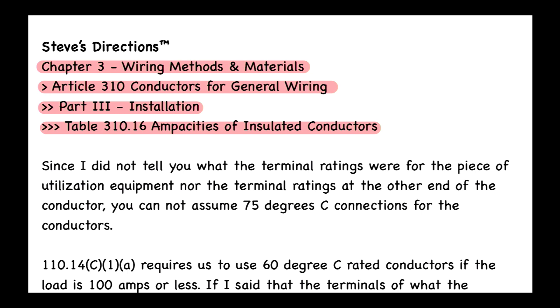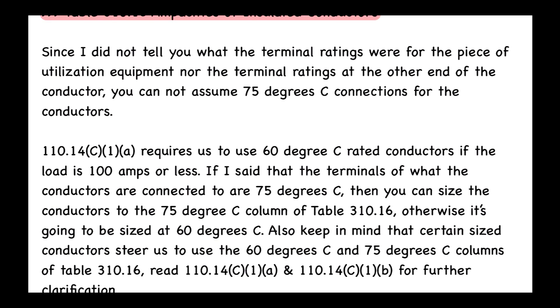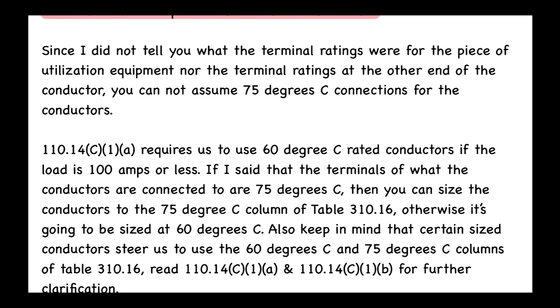Since I did not tell you the terminal ratings for the utilization equipment or the other end of the conductor, you cannot assume 75°C connections. You need to know what's on both sides of the conductor. If one side is rated 75°C but the other is only 60°C, you are limited to the 60°C column. Be especially careful about this on an exam.